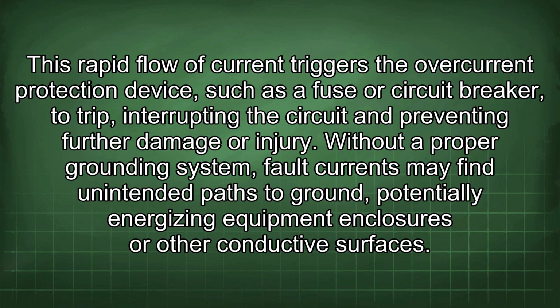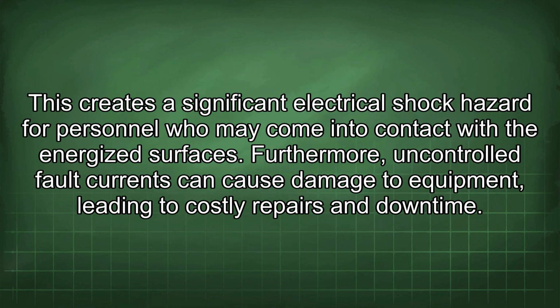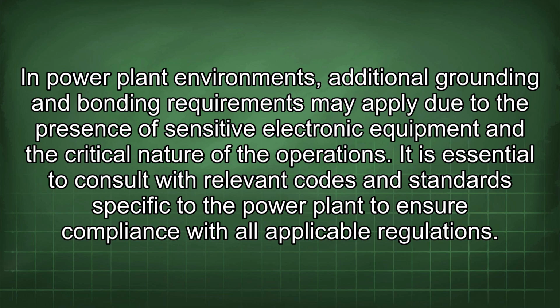Without a proper grounding system, fault currents may find unintended paths to ground, potentially energizing equipment enclosures or other conductive surfaces. This creates a significant electrical shock hazard for personnel who may come into contact with the energized surfaces. Furthermore, uncontrolled fault currents can cause damage to equipment, leading to costly repairs and downtime. In power plant environments, additional grounding and bonding requirements may apply due to the presence of sensitive electronic equipment and the critical nature of the operations.